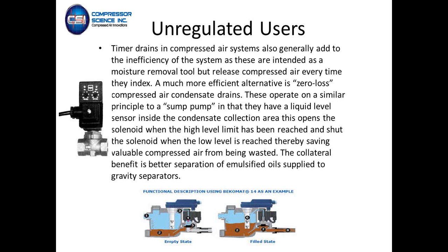The other thing you're getting as a collateral benefit: if you have oil-water separators in your compressor room that are collecting oil out of the condensate from dryers, filters, and compressors, then by not pushing 100 psi condensate out every time, you're reducing the emulsification of the oil. That allows better separation efficiency in the compressor condensate separator as well.